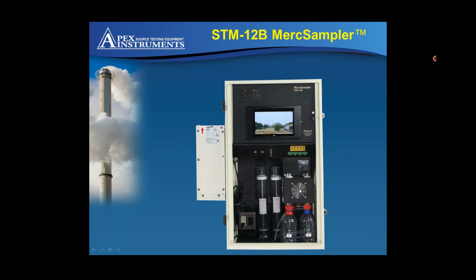We run a Stirling engine, which I can go into further in depth a little bit later. But that's our gas conditioner, our knockout for our moisture before we go to our dry gas meters for our volume reading, which is located up here in the console portion. We have our acid scrubbers here, which, after our chiller has our moisture knockout, we run the gas through as a redundancy. It helps protect the dry gas meters and all the internal workings, knocking out maybe a little bit of moisture if it's left there, or some of those nasties that might be left in the sample gas.